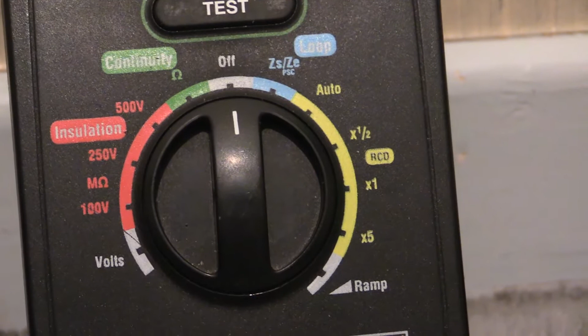Moving up then. So you've got the test button there, and you've got these 4 buttons here, F1, F2, F3 and F4. What they are for is they carry out a range of functions depending on what test you're carrying out. As an example, on certain tests, you choose a particular test, and if you press F2, it will lock this test button. The idea is that when you lock the test button, you can push it and it'll engage the test, and you don't have to hold that button down to keep the test going.